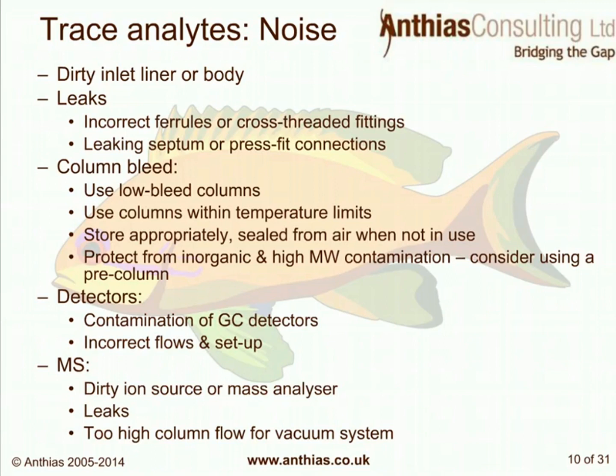Dirty GC detectors can also cause noise, with dirt bleeding into the signal. Incorrect gas flows or detector setup can lead to higher baselines and lower signal. With a mass spectrometer, a dirty ion source or mass analyzer can cause continuous background in mass spectra and chromatograms. Leaks in the mass spectrometer will desensitize it, and using too high a column flow for the vacuum system will also increase noise and reduce sensitivity.